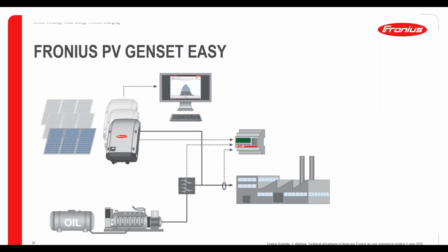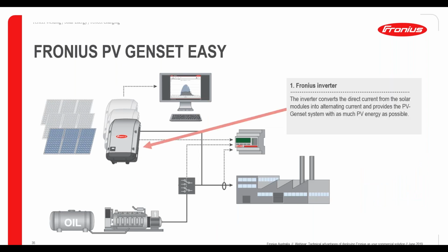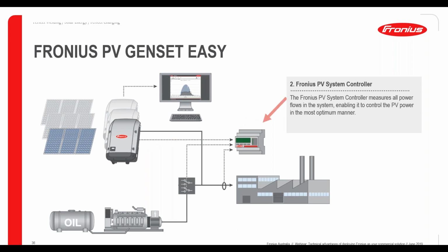The way it's all set up, we've got firstly the inverter, and hopefully everyone already knows what the inverter does. We've also got a Fronius PV system controller. This is specific to genset setups, and it measures all of the power flows in the system to control it and make sure that the power is being delivered in an optimal manner.